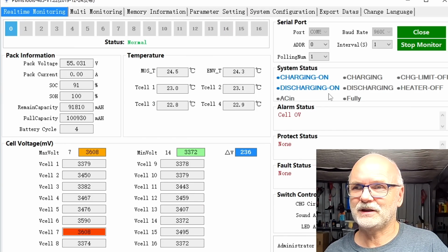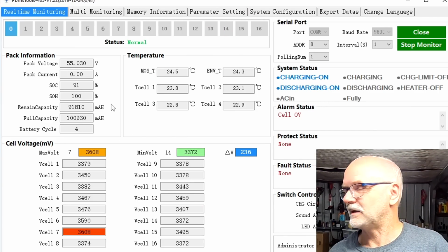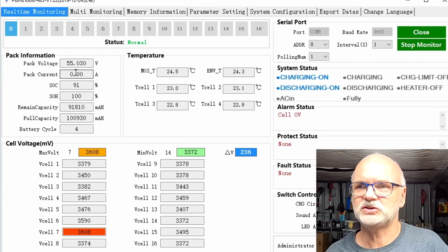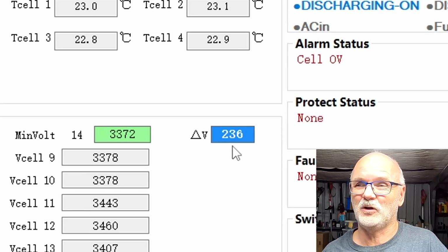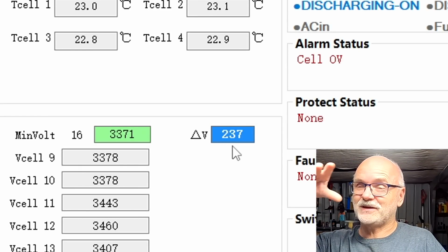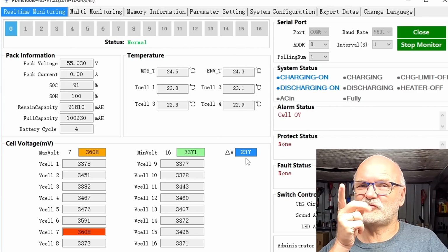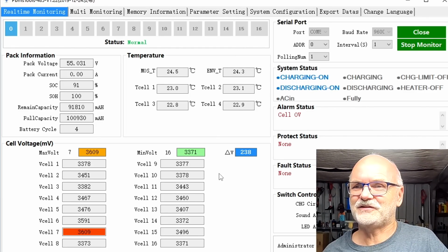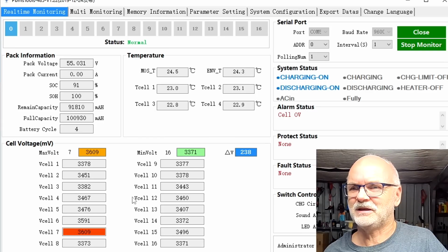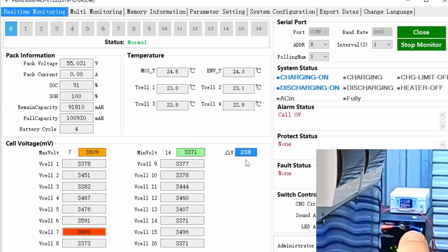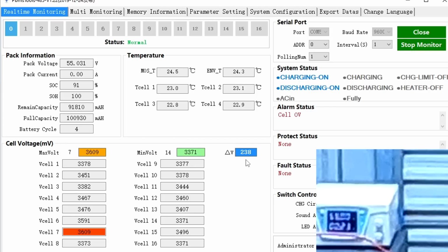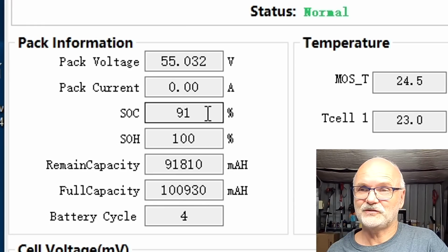Okay, anyway, we want to have a look at the parameters. As we can see, the BMS has actually stopped charging. We are at 55 volts already, and we've got a deviation of 236 millivolt. This is as the battery came to me. And as you know, we have done 1 or 2 discharge tests so far, and I cannot see any balancing function happening here. I don't know if the cell number 7 gets actually balanced now. The only thing I can see is that my deviation actually increases. I can see there on the power supply we're still charging with 230 milliamps. It shows us the state of charge at 91%, but I believe we are far higher.